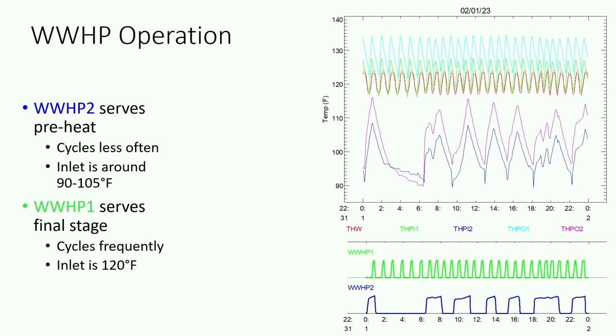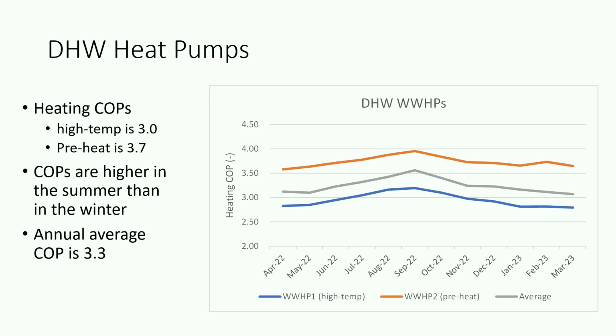So when you have a preheating tank, the heat pump serving the preheating tank has colder water, runs longer, and cycles less. Whereas when you're trying to maintain the finished tank, you can see the cycles. So the bottom line is that you do have these two different stages of tanks, and the heat pumps behave differently in those 2 stages. So here is kind of the COP. The blue one is the high stage tank, or the final tank. The orange one is the preheat tank.